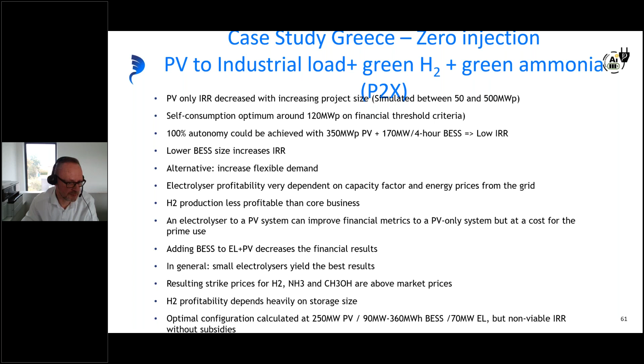In the end, we had an optimal configuration at about 250 megawatt PV, 90 megawatt battery for 4 hours, and a 70 megawatt electrolyzer, but still with a non-viable IRR without subsidies. It was a positive business case, but too low an IRR for an investor to actually start working on. Still, it was the most optimal case at that moment, and this can then be used, for example, to ask for grants and support from the local or European government.